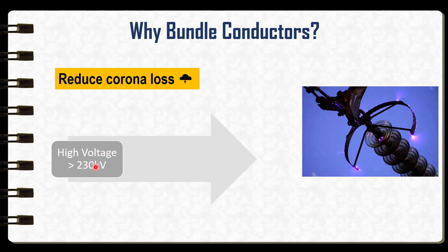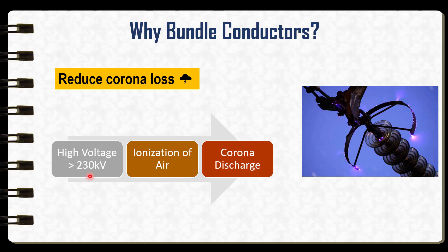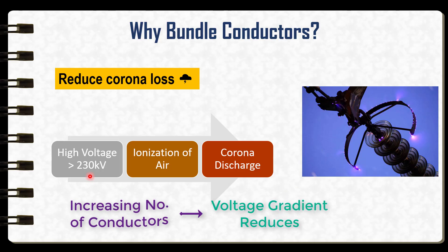At very high voltages, above 200 kilovolts, the electric field around a single conductor is intense causing the ionization of surrounding air, leading to corona discharge. So by increasing the number of conductors per phase, the voltage gradient around the entire bundle is reduced, which decreases corona formation and power loss.